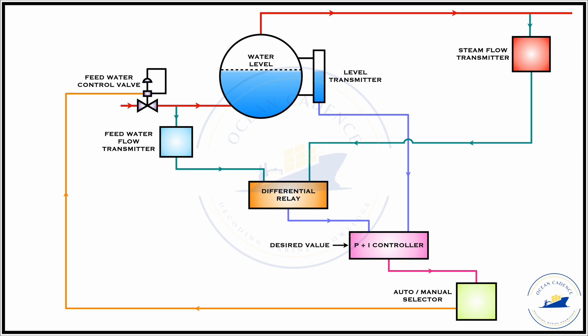What this does is that at any point of time the response time in filling your boiler and your boiler getting empty is very small which means there is no differential lag that is existent between the full condition and the low level condition. And by doing so what we do is that we make sure the steam pressure fluctuation in the outlet line that is the main steam line is not very high. So under constant demand also and under variable demand also your boiler will be able to maintain a constant steam pressure output with a relatively lower variation in the flow of the feed water with this particular circuit.